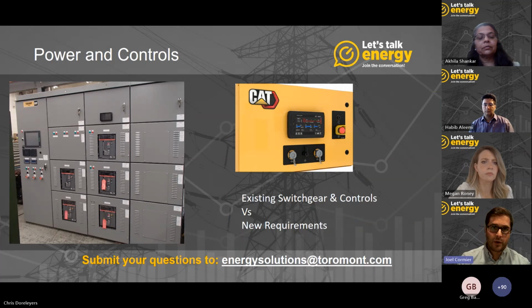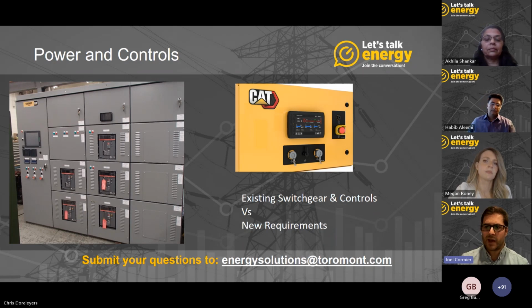So now we'll look into more of the power side of things. On the power side, an analysis would have to be completed to verify whether the existing switchgear on site had the extra space or the extra capacity to add the new sources. If not, Toromont can provide custom switchgear solutions that we manufacture in-house to accommodate whatever the customer's needs may be. For controls, Toromont would provide a microgrid controller that would interface with all the sources. So it would talk to the renewable sources like the solar or wind, the utility, the battery energy storage, any gen sets that may be at site, and then it would dispatch all those assets accordingly.